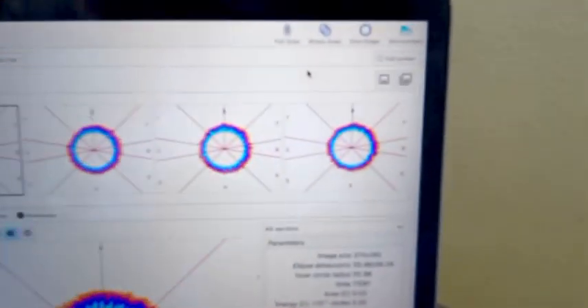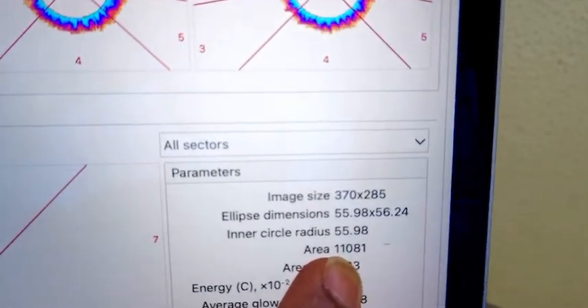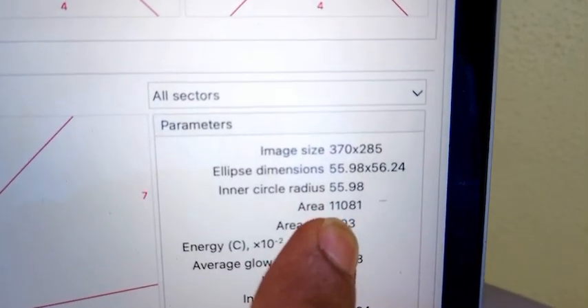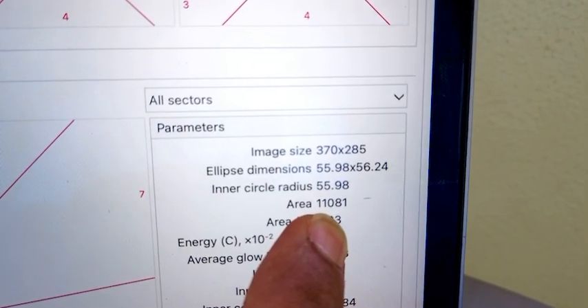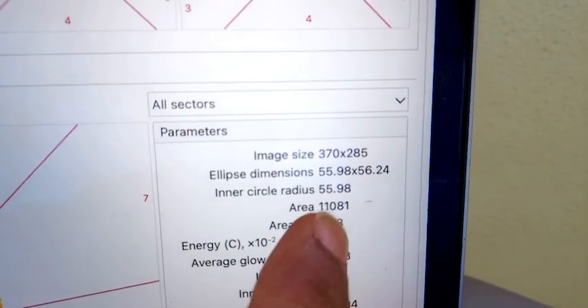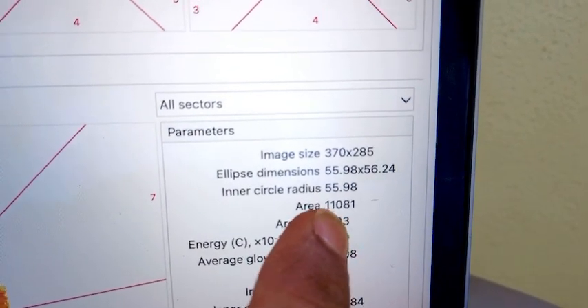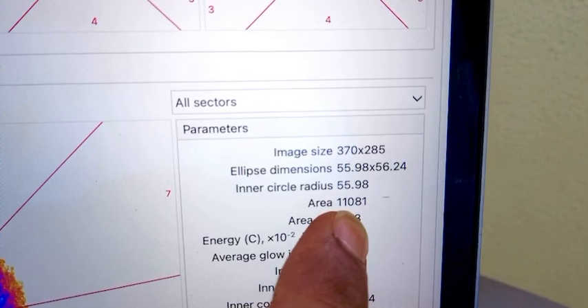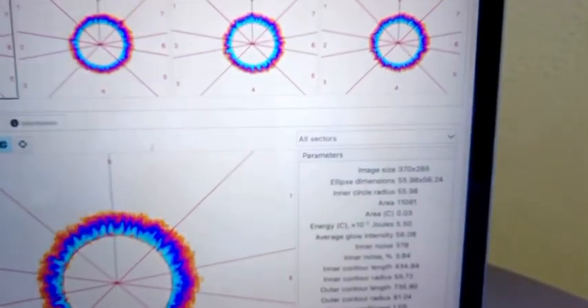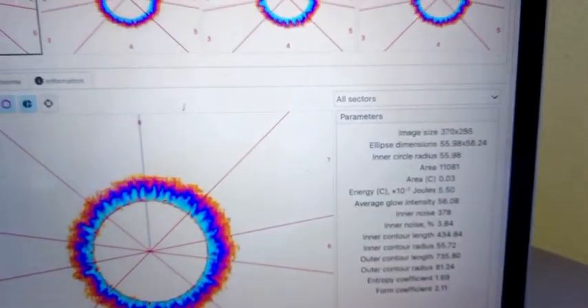that, and then see over here it's going to give me an area value. See here, it says area 11,081. As long as this value is between 11,000 to 12,500, then that's a sign of a good calibration.